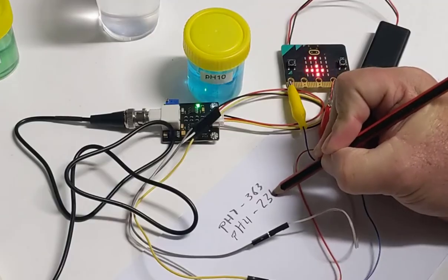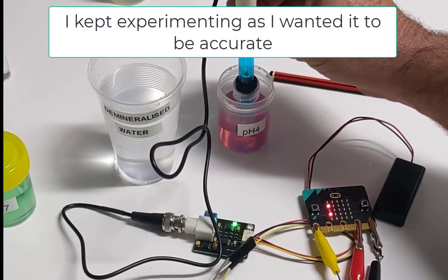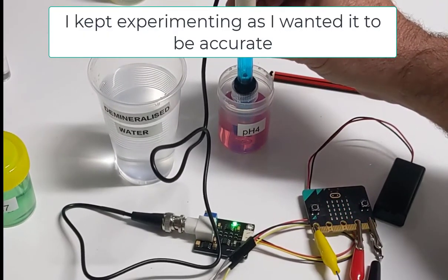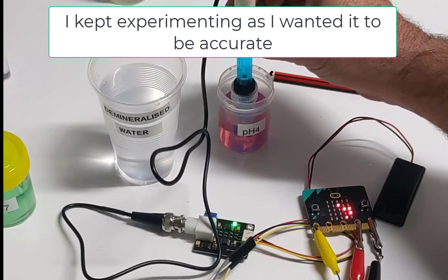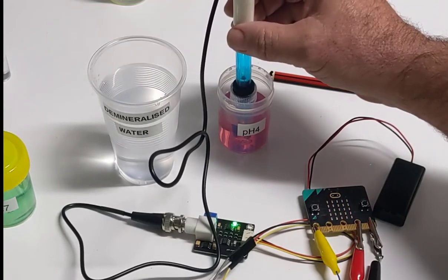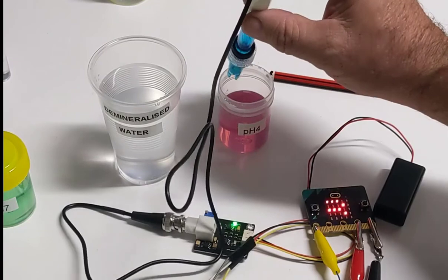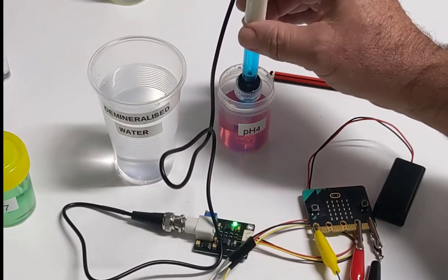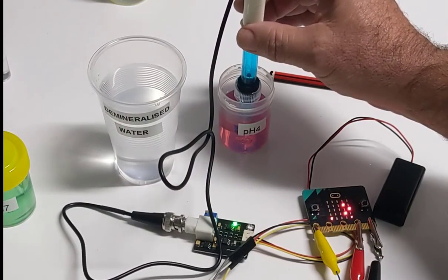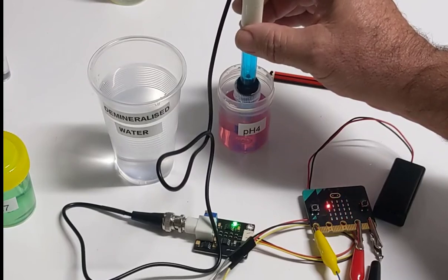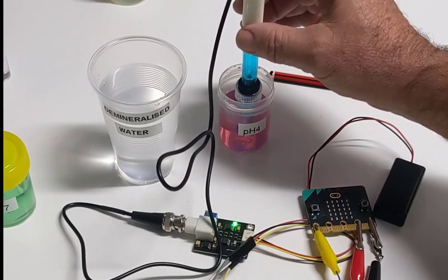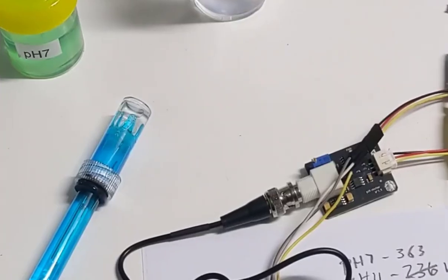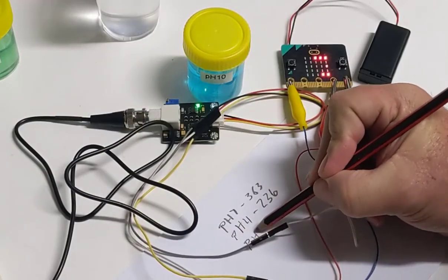Let's make it 236. So if I place it in the pH 4, I get a value of about 193. 191. So I can see that I've got 188 three times in a row, so let's use that. So that means I can change my pH 4 value down from 236 to 188, which is a little bit more accurate. And then pH 10.